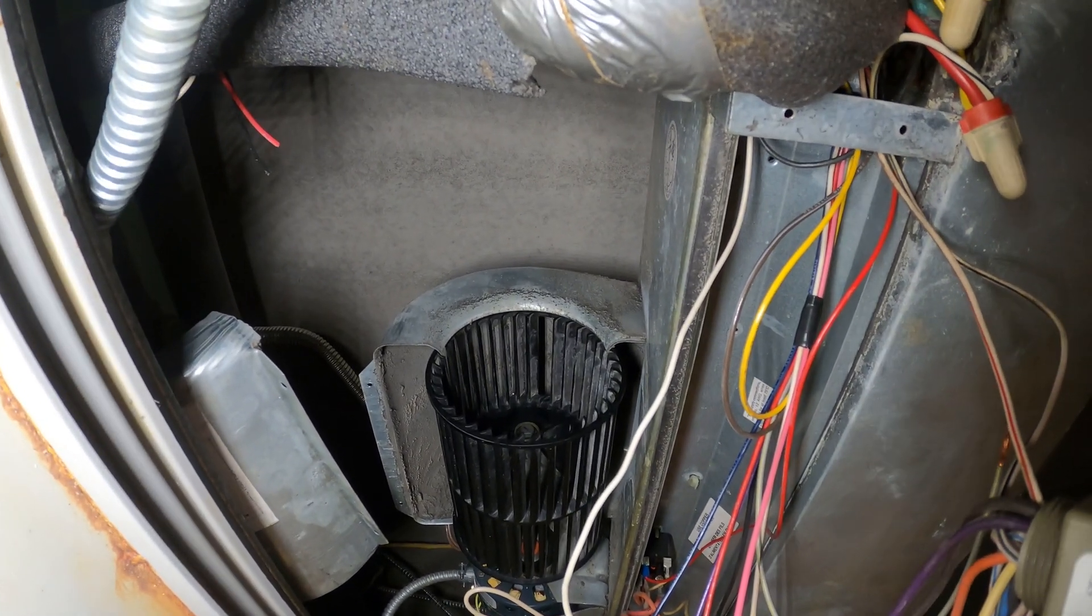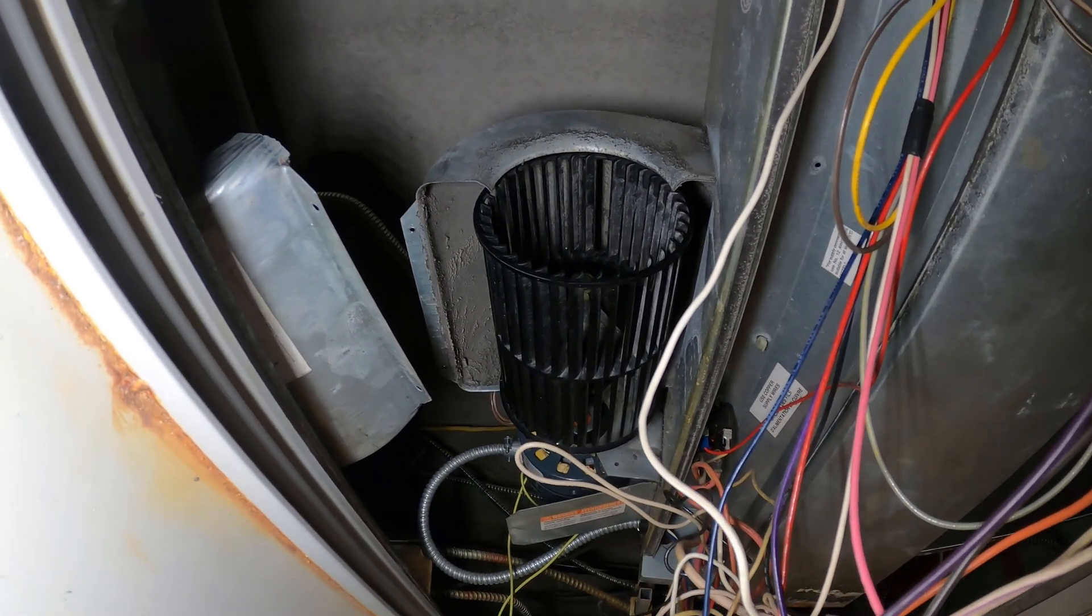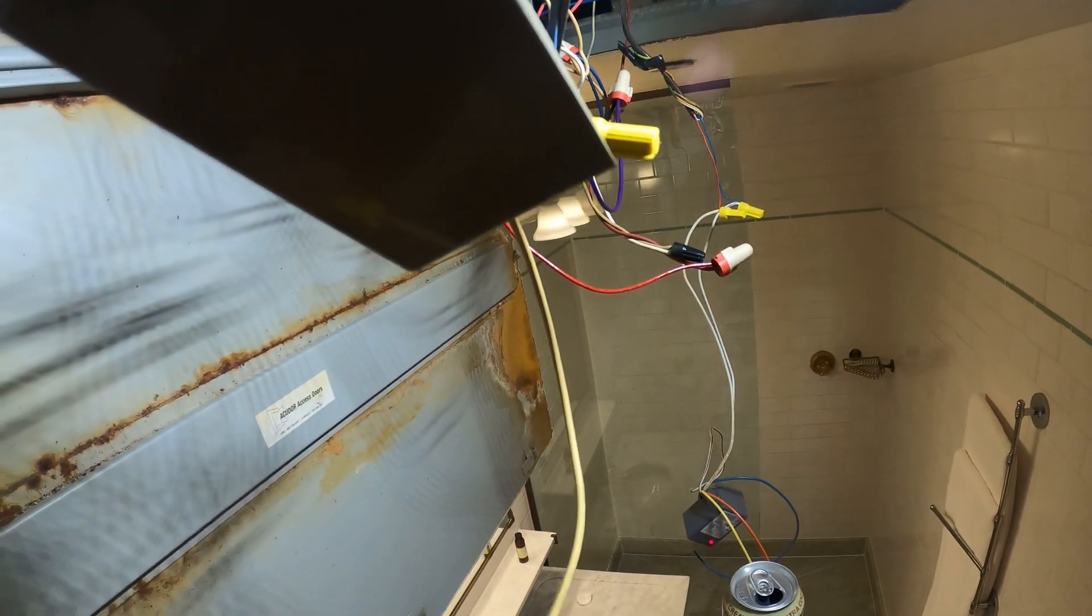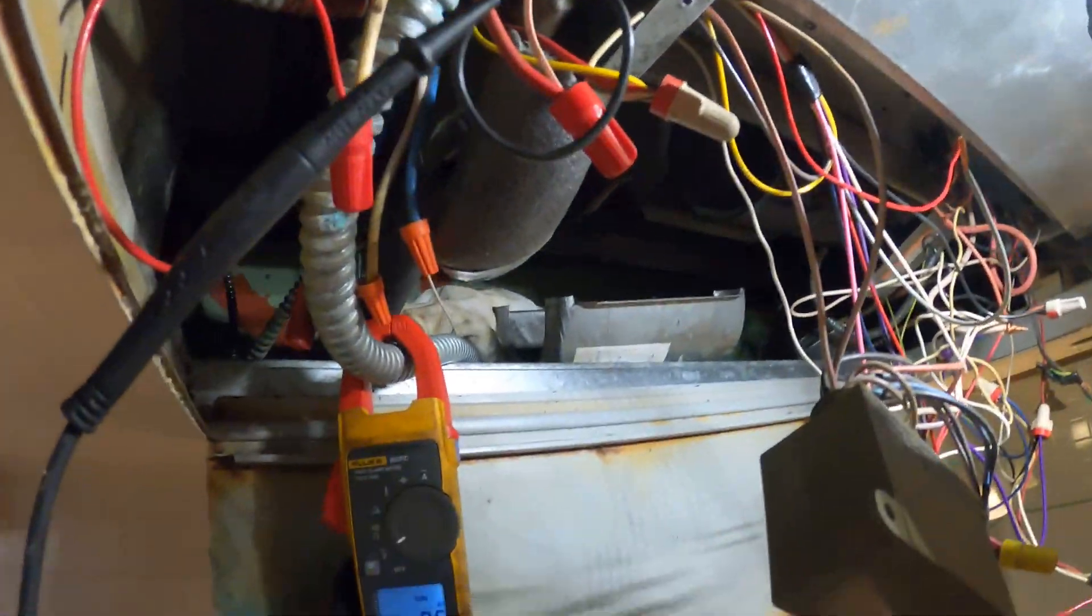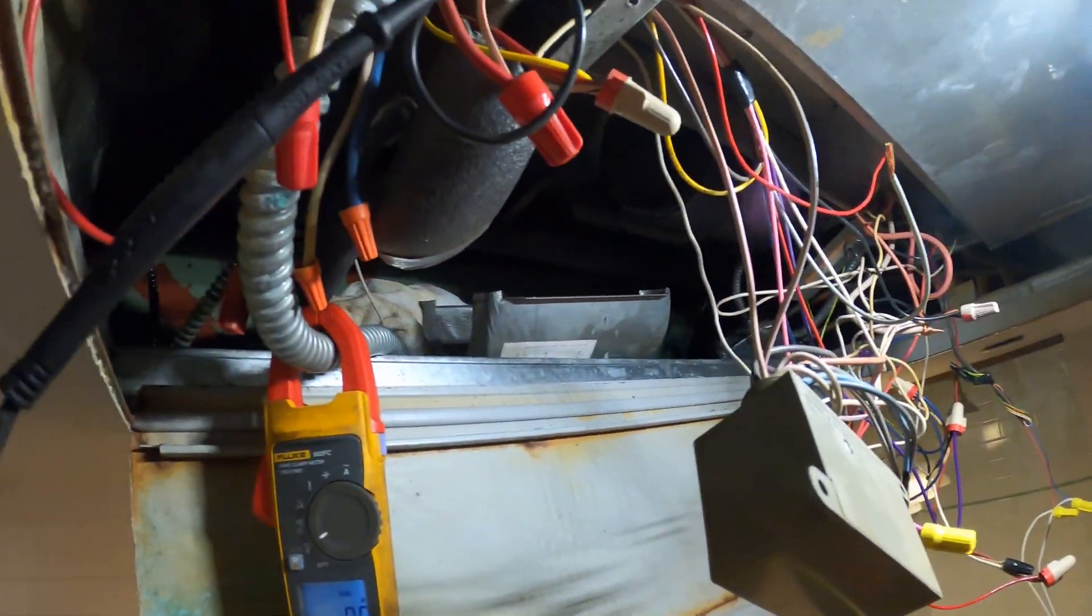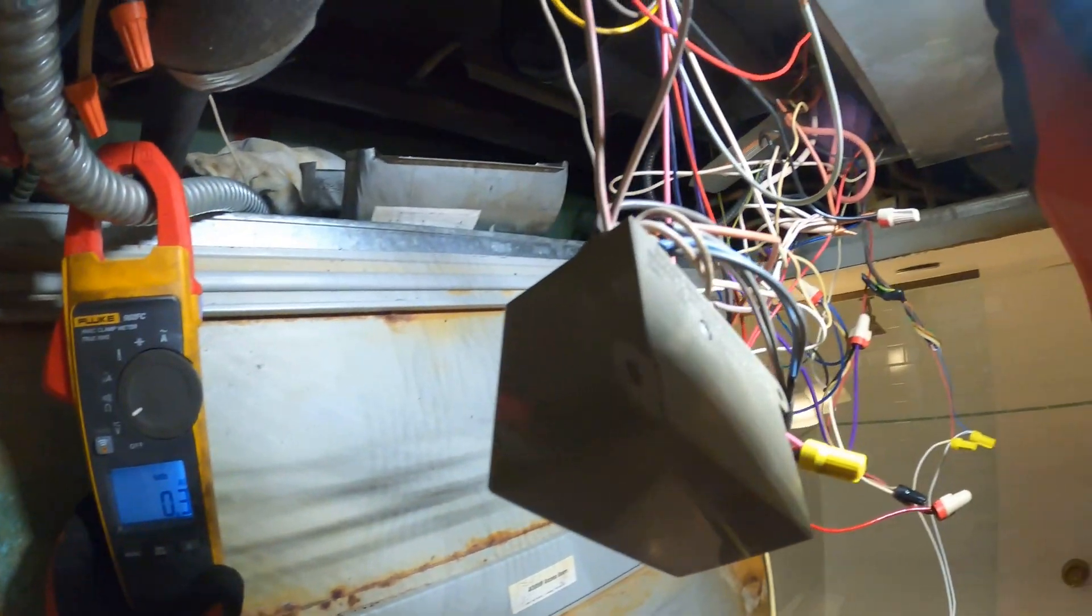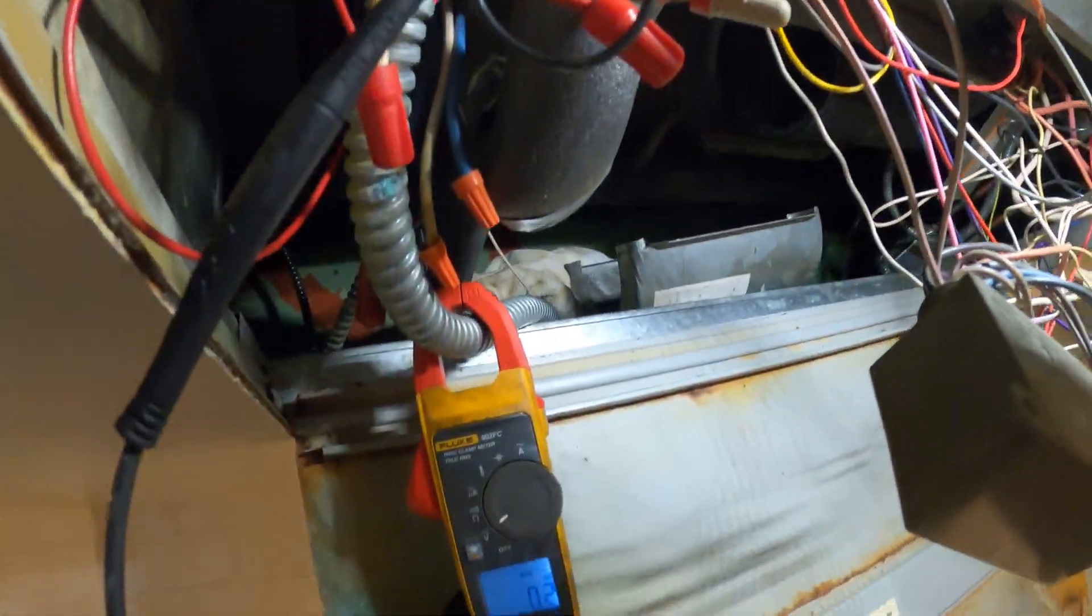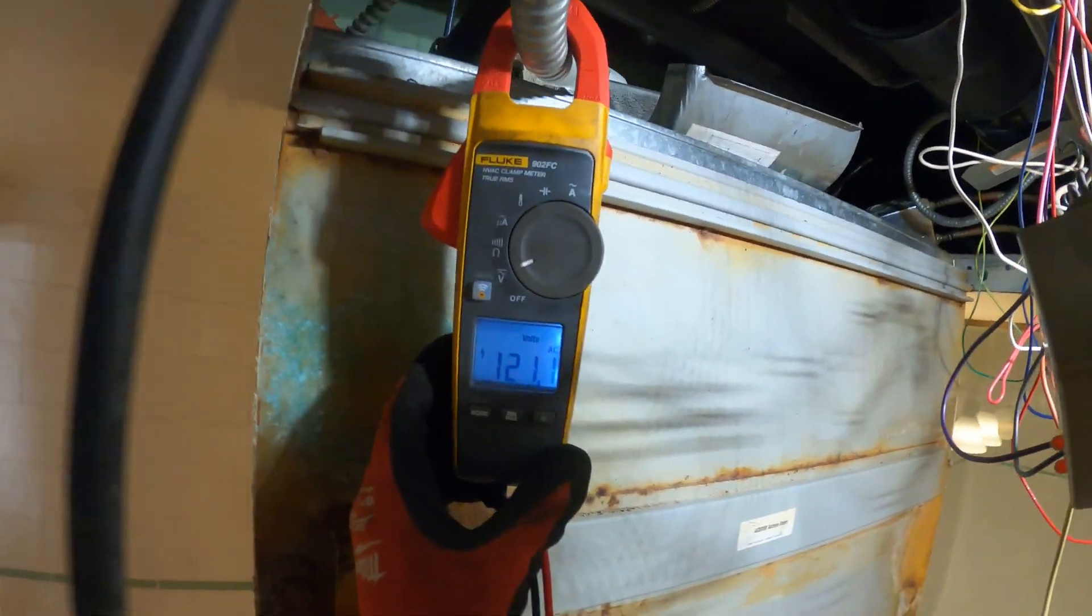It's a two pipe fan coil system. But, we are in cooling mode. So, chiller I believe should be on. So, let's see. Well, we could put our hand on the pipe and see. Alright, my guy's about to put it in cooling and lower the thermostat. So, this is our wire for cooling. It's in cooling? Yeah. Got nothing. Actuator's closed. Maybe that's the wrong wire. Can you put it in heating? Got it. We got nothing on this wire. That actually might be heat.